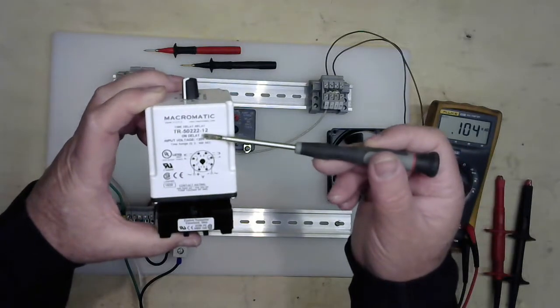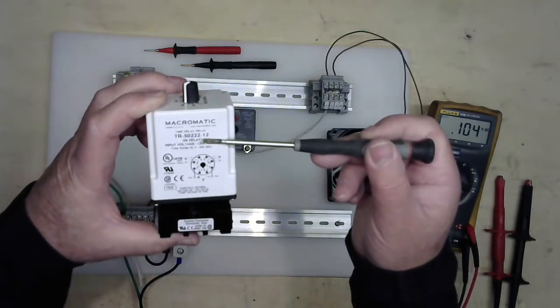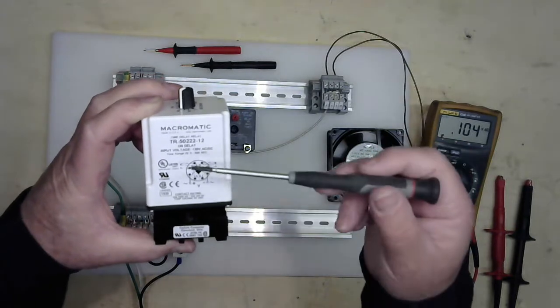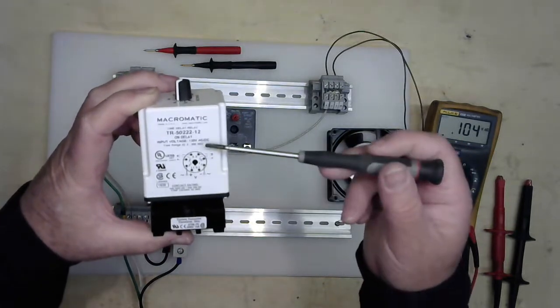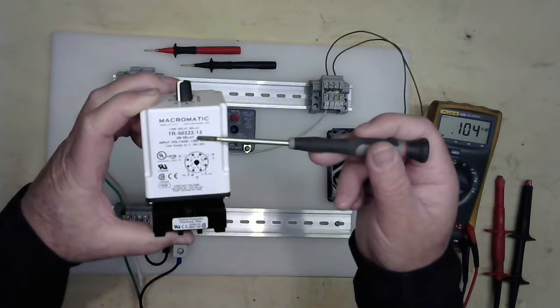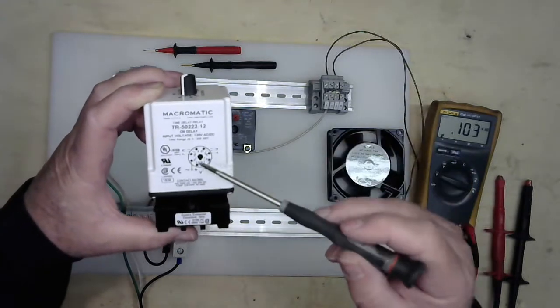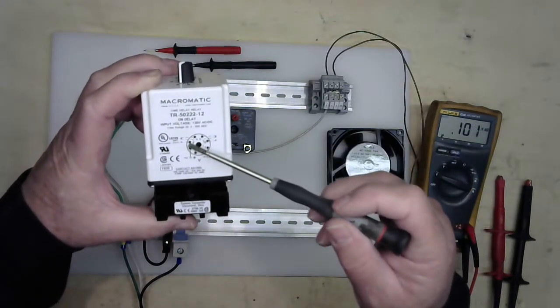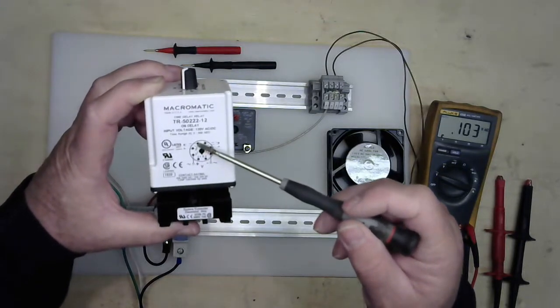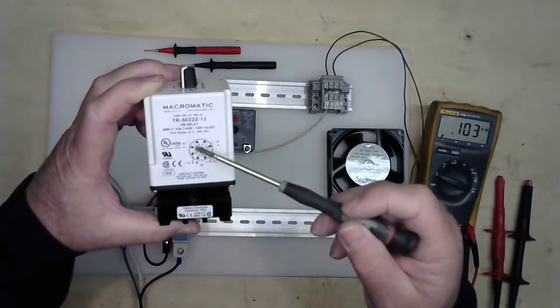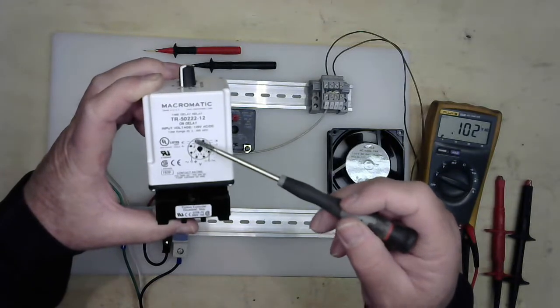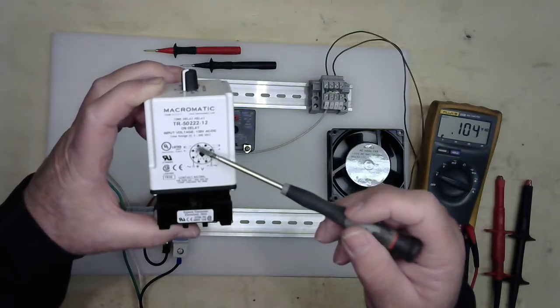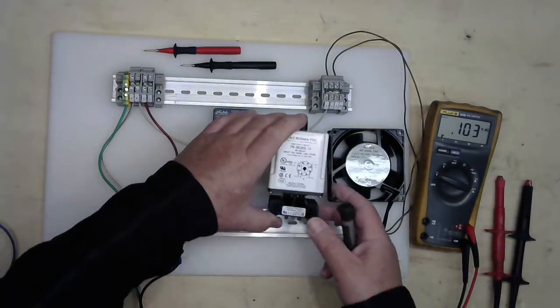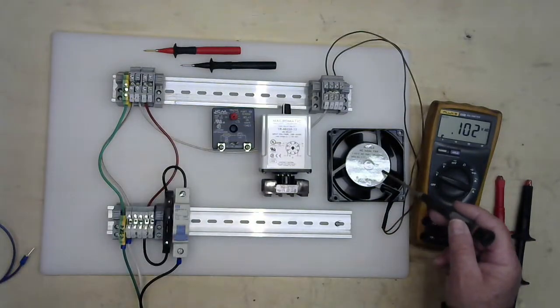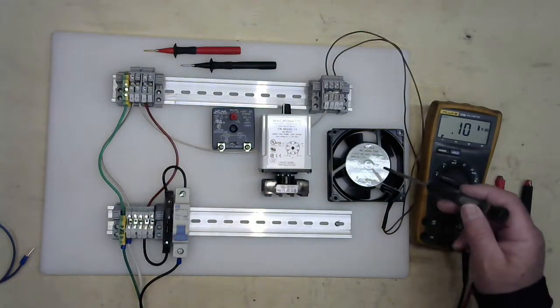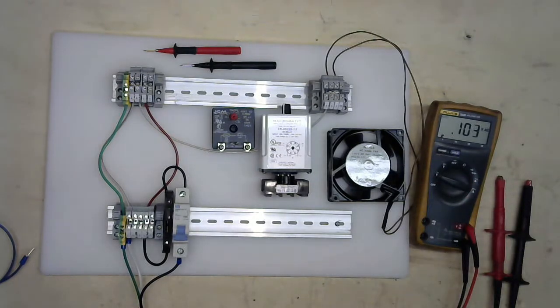This is an on delay timer. These are very common where maybe you want to have one motor starting, then you want to wait so many seconds later to have a second motor starting. You can have one application starting first as a part start, and you can go to the second application where you can go to a full start line contactor. So maybe you'll have two different loads on your normally open, normally closed. Okay, this is my fan that we're going to be using as a load situation. So in a minute, I'll demonstrate both relays for you.